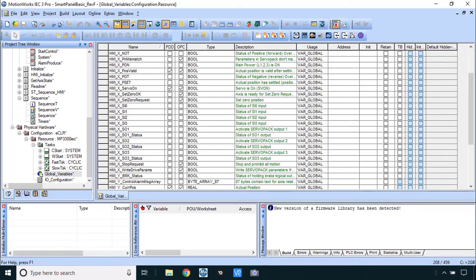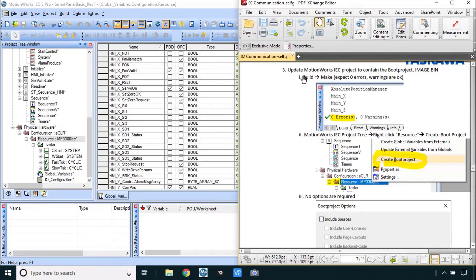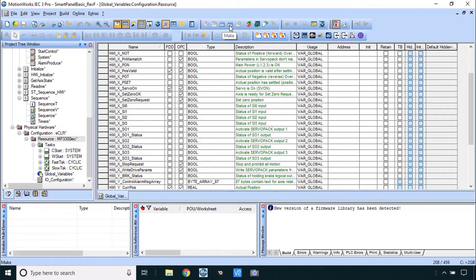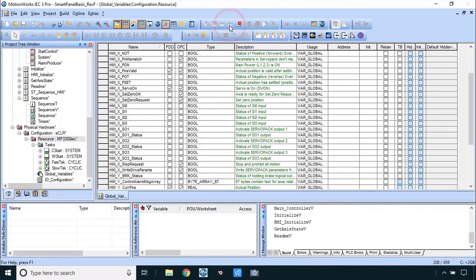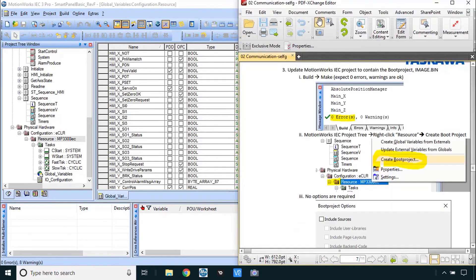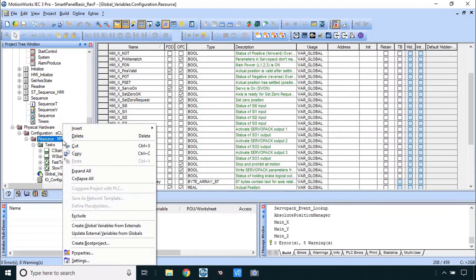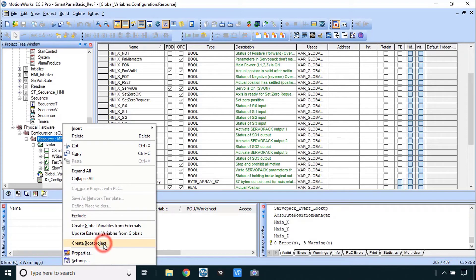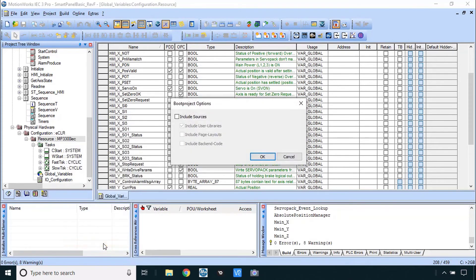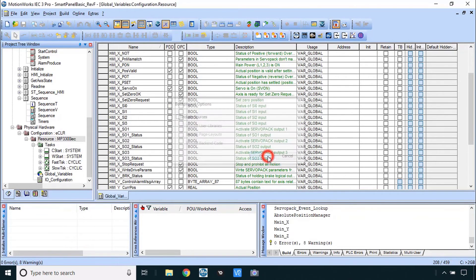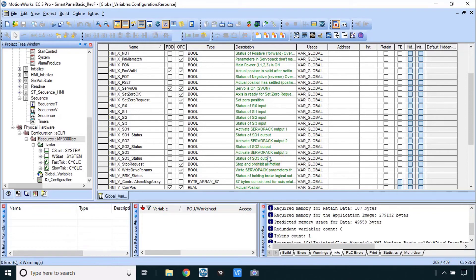You'll go into MotionWorks IEC. Like it says here to create that boot project first step is to build. You can do make or rebuild project. That's done. And then you can right click on the resource to create boot project. Let's do that here. Create boot project. If you don't make first this will not appear. So be sure you make first. You don't have to check that box. We'll just click OK here. It happens really quick behind the scenes.